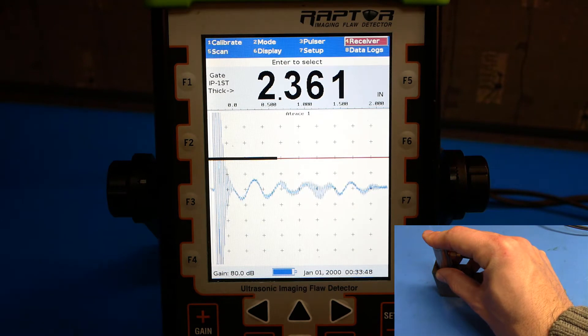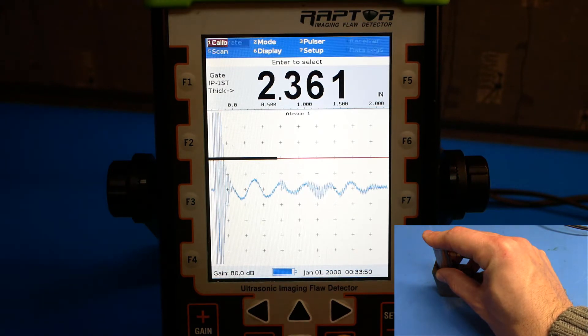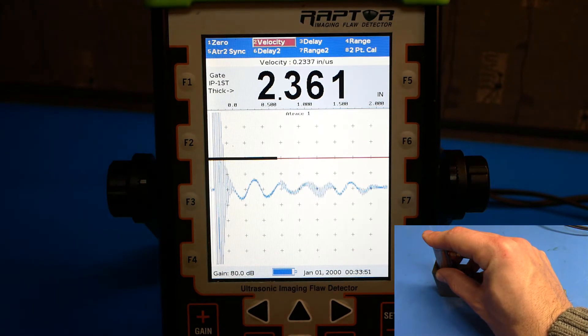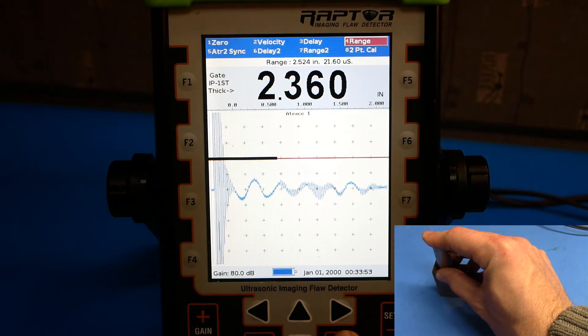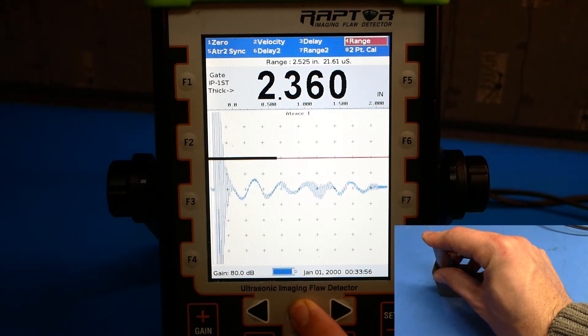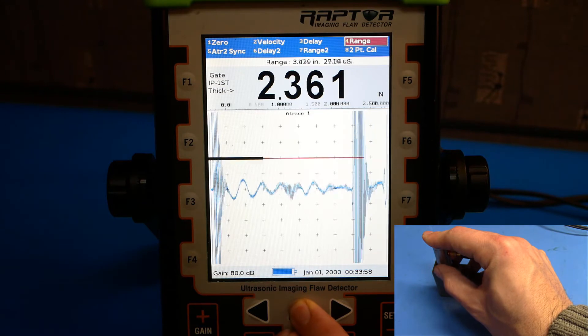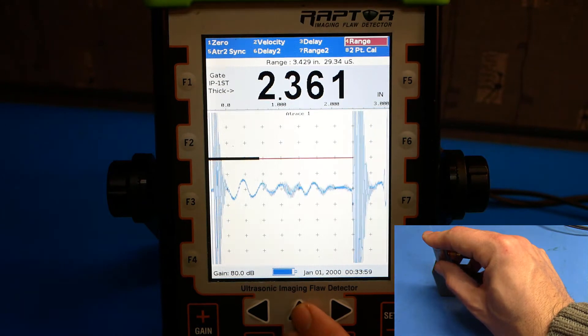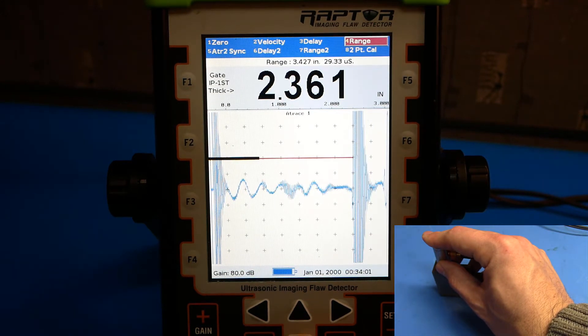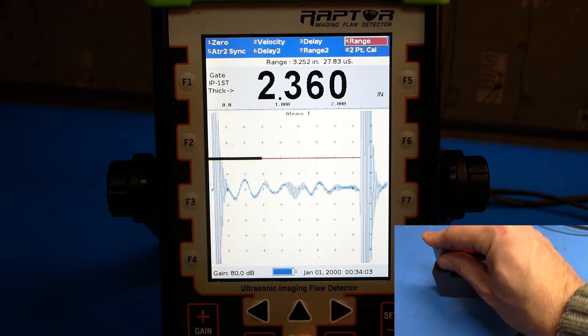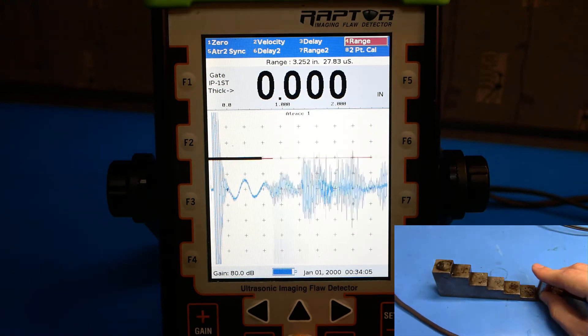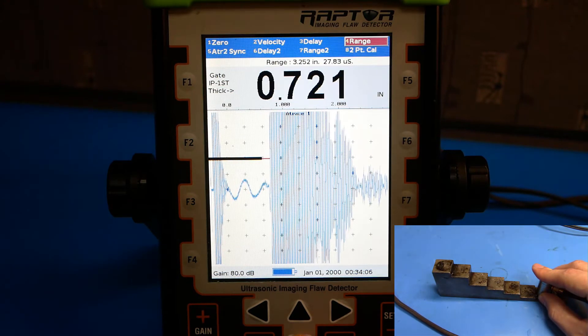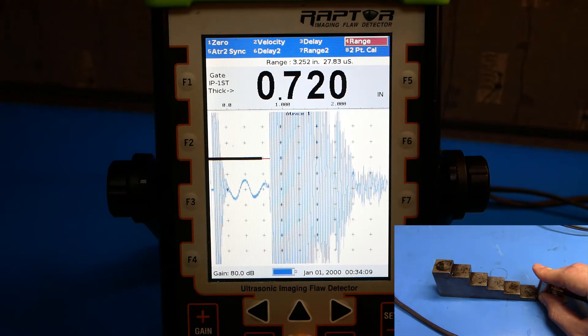To fix this, we'll go to calibrate. We'll go to range. And we'll use the up and down arrow keys to adjust the range until we see an echo from the top part of the step block. Go back to the lowest bound on the step block to make sure that we're still within bounds.